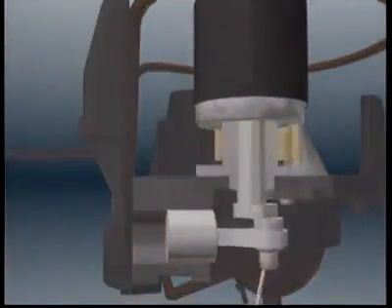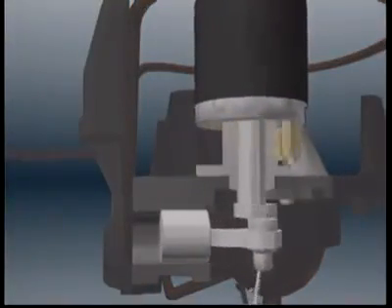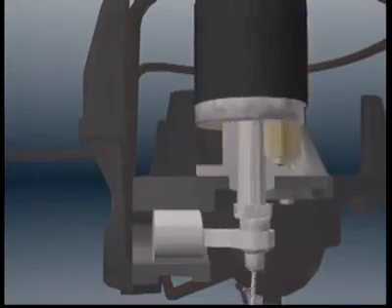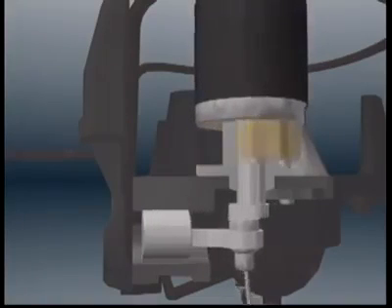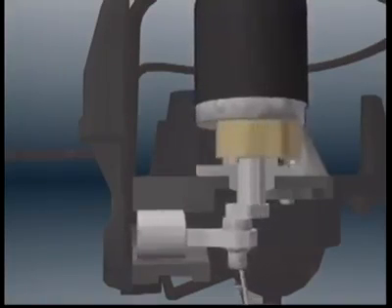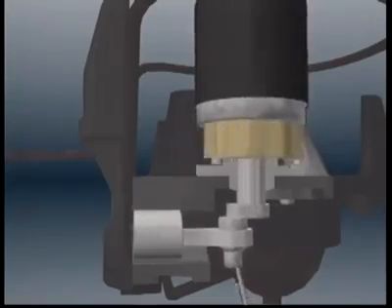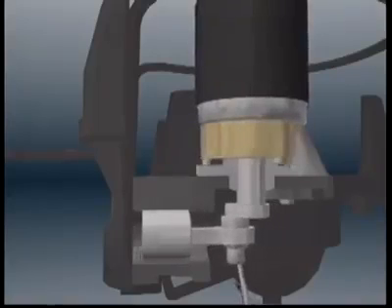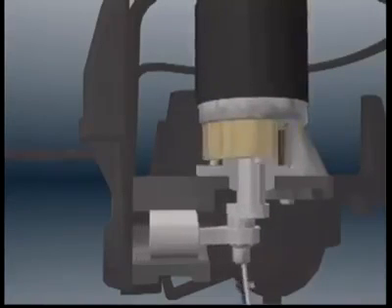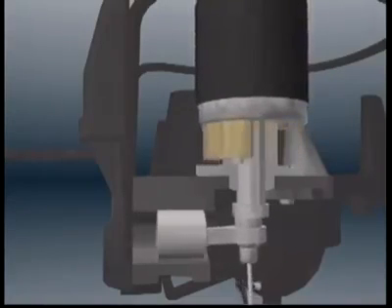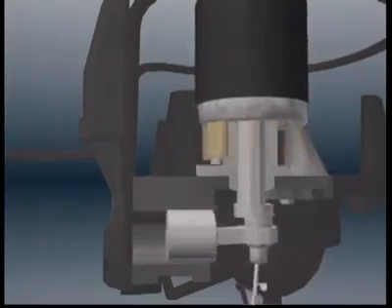The rotor and shaft drive a piston back and forth in the compression cylinder. The piston draws refrigerant into the cylinder on its pull stroke and forces refrigerant out on its push stroke. The piston employs a patented design that increases efficiency by directing the refrigerant toward the exhaust valve. This is the pump action of the compressor.